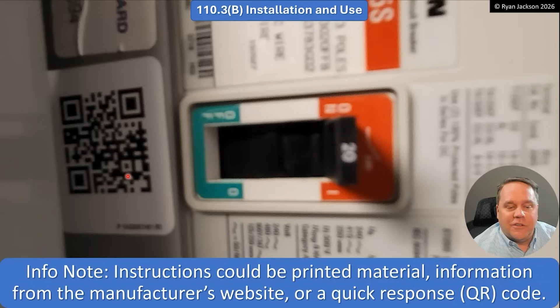So there you have it. Follow instructions, folks. And if the instructions tell you to do something that would result in a code violation, then you can't do it. You just can't. So there's some equipment, and I want to dance around this issue because you probably know what equipment I'm talking about. There's equipment normally installed in a garage or outside that says do not install this on a GFCI. All right, well then you can't install it outside or in a garage. You might have to install it in your bedroom. So you've always had to comply with both requirements, the code and the instructions. That didn't change, but now we made it very, very clear.